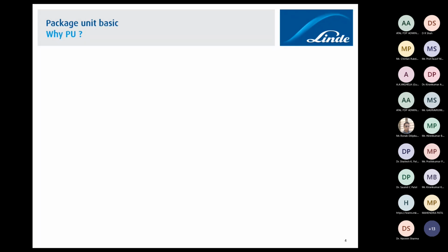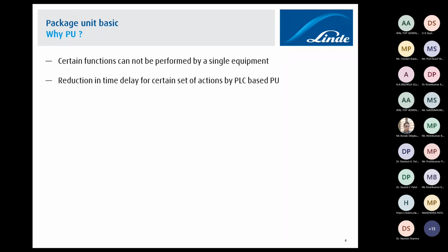Okay, so why do we need package units in industries? Certain functions cannot be performed by a single piece of equipment, and that's why we are clubbing all this equipment together to obtain a certain function. Reduction in time delay for a certain set of actions, that is a programmable logic control based package unit, because sometimes, in spite of having a lot of automation from the DCS control room, you cannot achieve the target operation within the microsecond. So whenever a certain operation must happen within the stipulated time in a microsecond, then you need to have a local operation or a PLC based package unit.